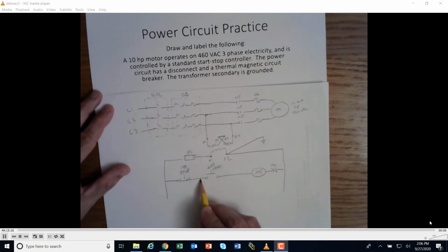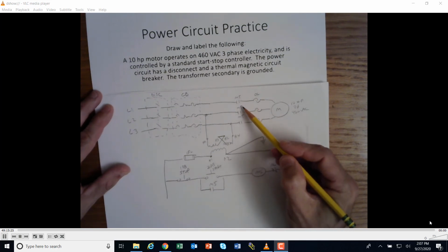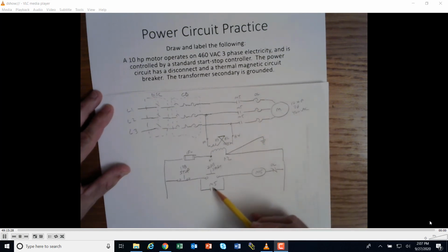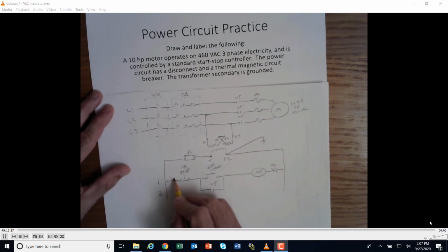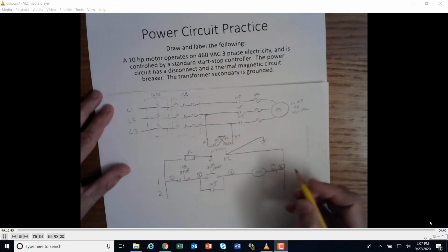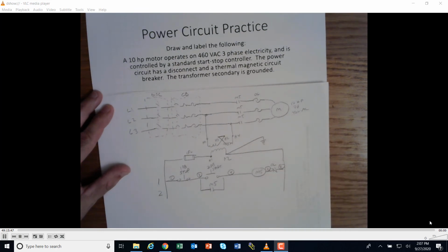And then, so what do I need here? I need memory. So we're going to use the auxiliary contact from that motor starter. There's 4 contacts. Your 3 main contacts for the power circuit, and then your auxiliary contact for holding. And that looks pretty good. We just need to do our labeling. 1, 2, wire 1, wire 2, wire 3, wire 4, wire 5, and then my motor starter is control's rung 2 here, so 2.